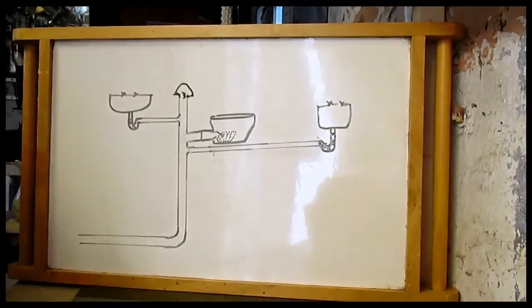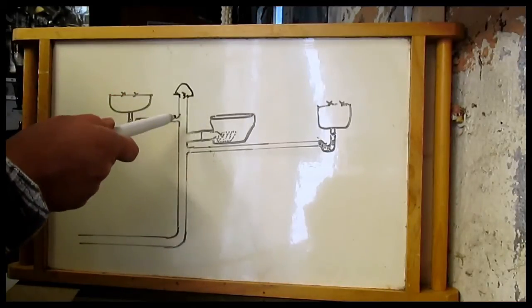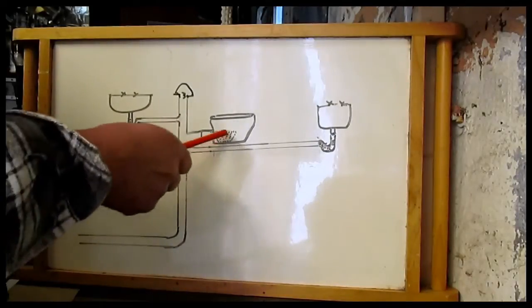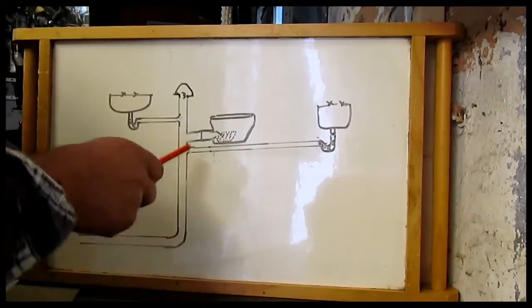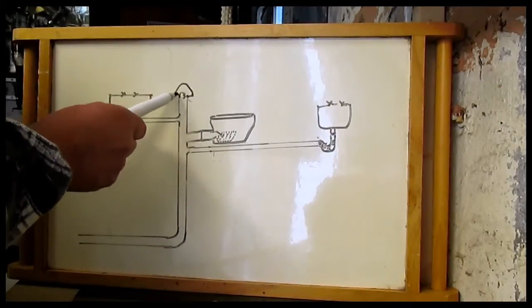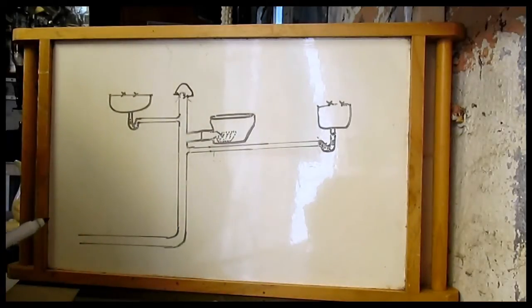And inside there is a mechanical device which will let the air go in but won't let the smell out. So if there's something sucking on there, if that's been put in and it's pulling down and it's trying to suck this out, a valve will open up in there which lets air flow in and it will stop that sucking of the traps off.